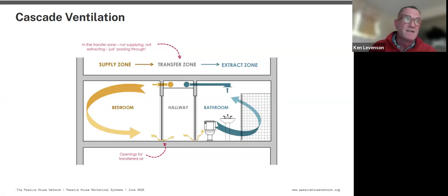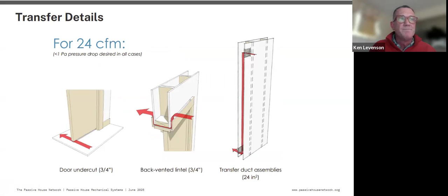And the key part then is if we aren't supplying everywhere, we need to make sure that it has a pathway. The air can't be stuck and we can't compartmentalize the space. So if you need to compartmentalize, we're going to need to have supply and extract in the same place. But we can do it architecturally and with undercuts around frames. Could use something of a transfer duct within the assembly or have a more traditional transfer duct.